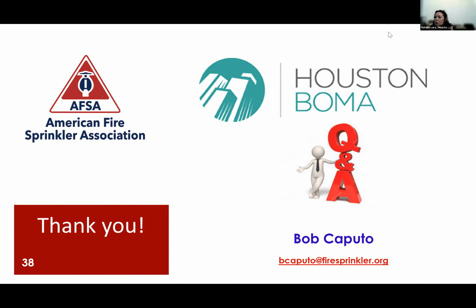One more came up. Talk about flammable liquid storage and what systems are required for those. Also, is there a volume of flammable liquids that triggers high levels of suppression? Yes, that's a great question. So combustible and flammable liquid storage is covered by NFPA 30 and NFPA 30B. That's a whole different cat. When we get into high hazard situations like that, there's going to be multiple things that aren't just fire sprinkler system related. For example, secondary containment.